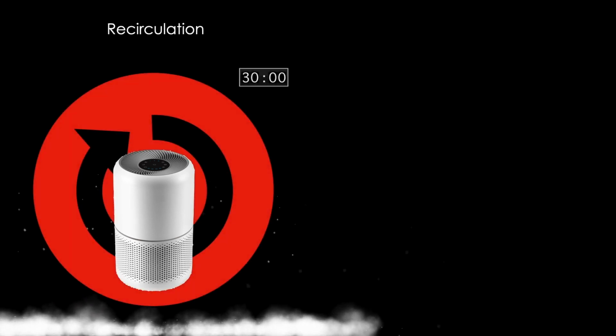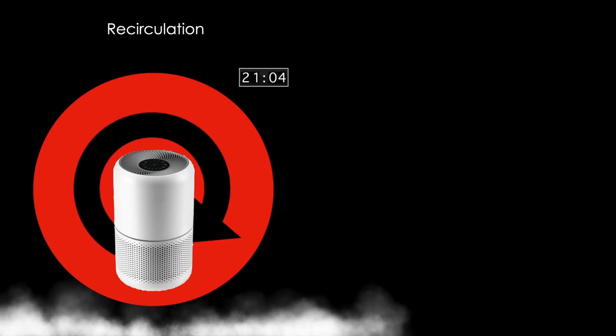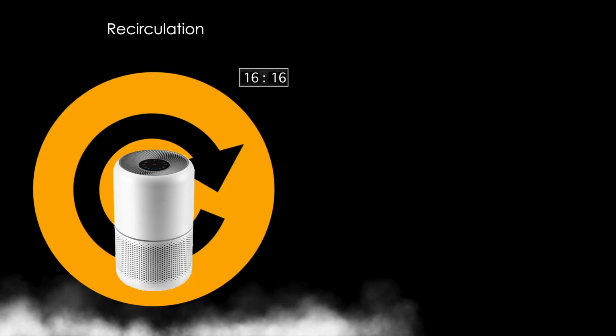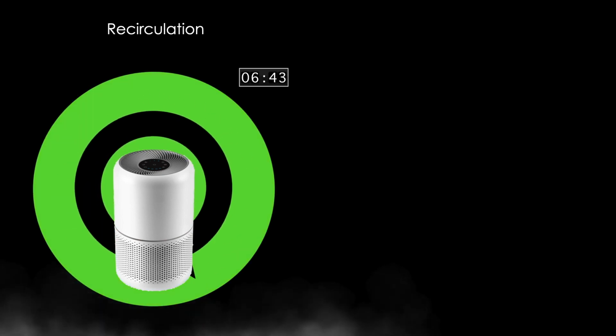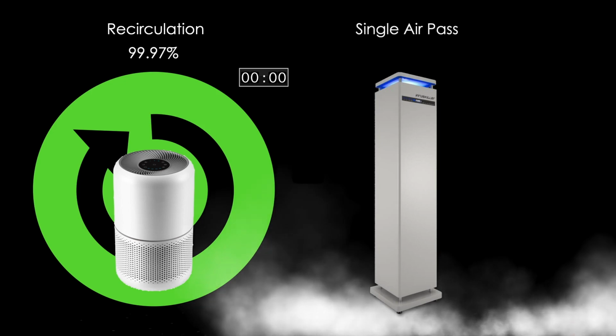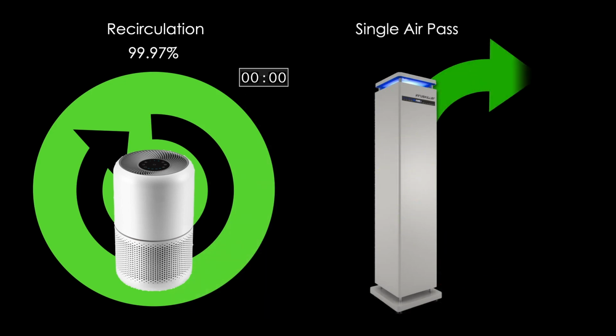So to take it one step further, because there can be a little confusion, not many talk about the single air pass. But a lot of these systems, air filters, consumer items, are put in a room with contaminants. The particle counts are made, and then a timer keeps track of it, and maybe 30 minutes later they go in and do a particle count as well. And the air keeps circulating and circulating. So at whatever time period they choose, they come out and they get 99.97%.